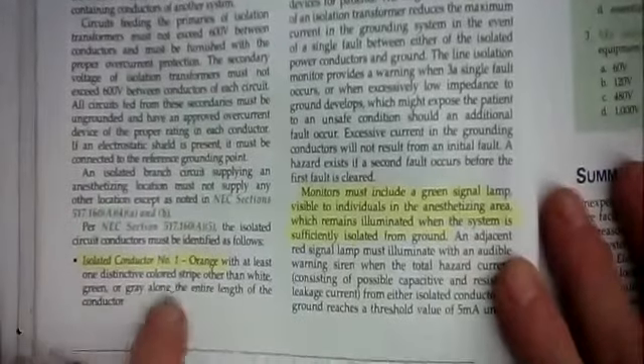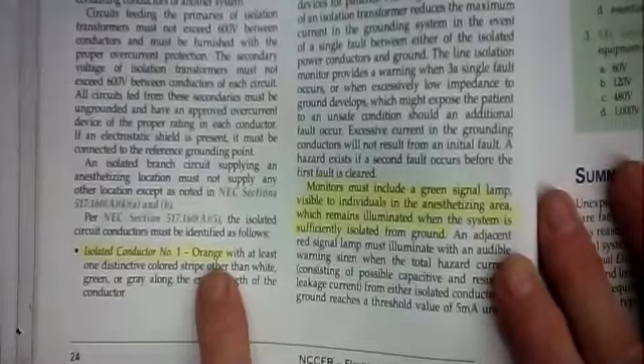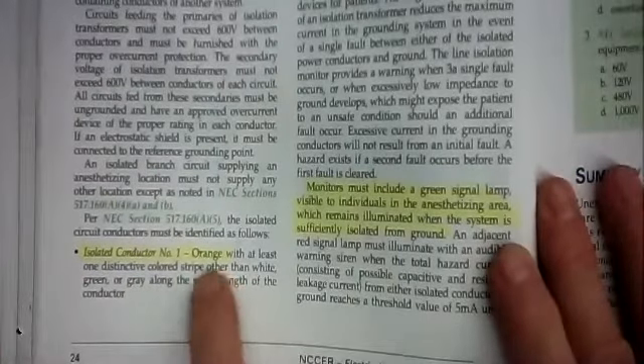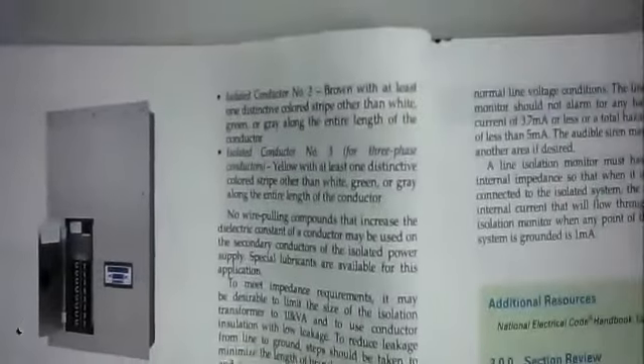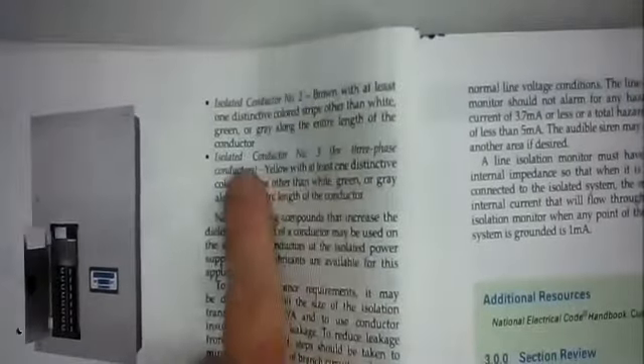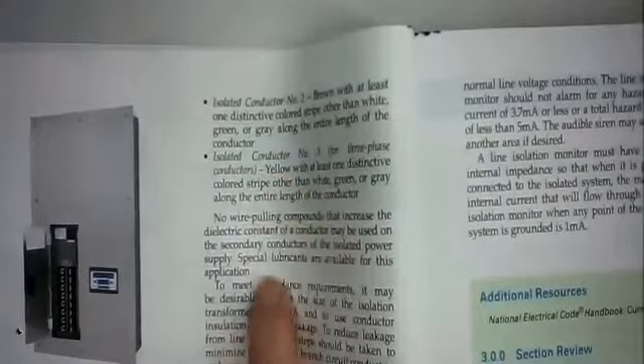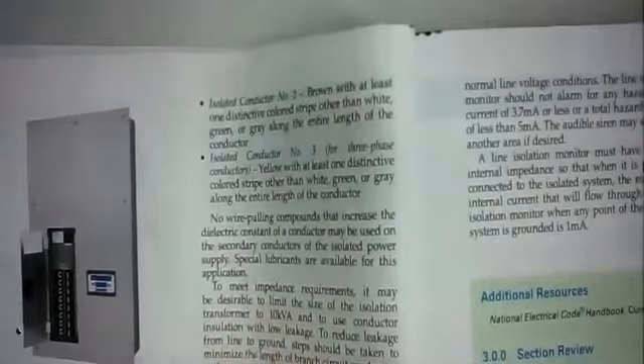The first conductor, number one, is orange in color. Instead of brown, orange, yellow, it's orange, brown, yellow. The first conductor is orange. The second conductor is brown, and the third conductor is yellow. Orange, brown, yellow instead of brown, orange, yellow, okay, of the isolated conductors.